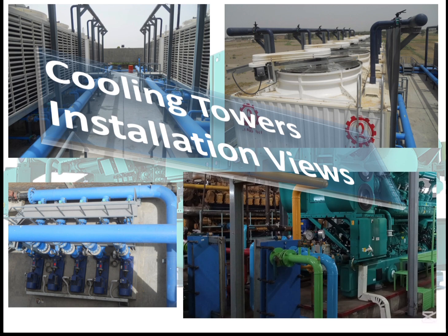If it's a closed circuit, tropical areas. But if it's radiator, if it's a cooling tower, then the installation procedure is a bit different. We need to install the plate type heat exchanger. So the genset connection will go to the plate type heat exchanger or LT1 heat exchanger. From those heat exchangers, hot and cold water will go to the cooling tower through a circulation pump. That will be the basics for the cooling system.